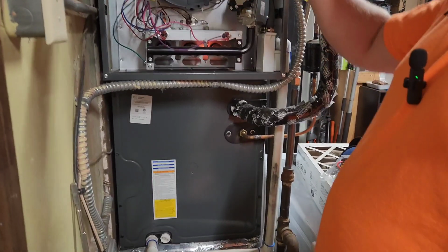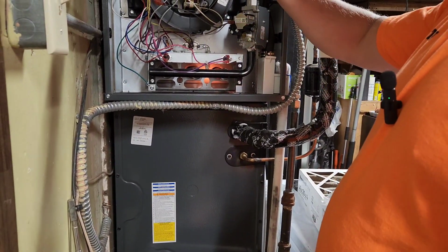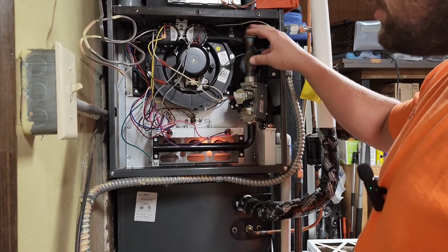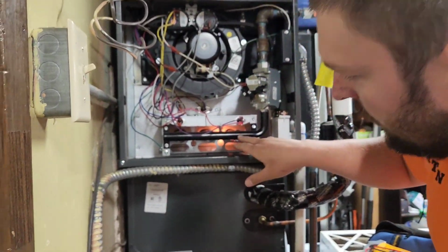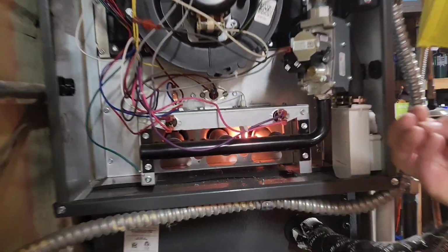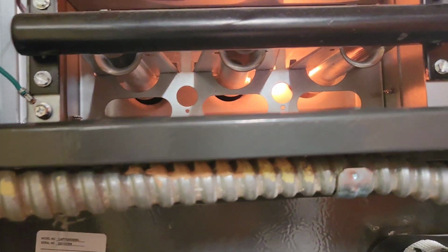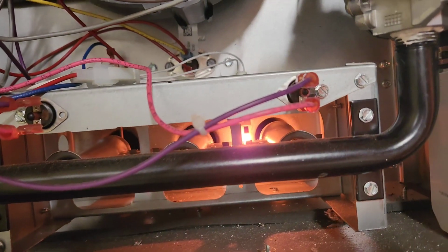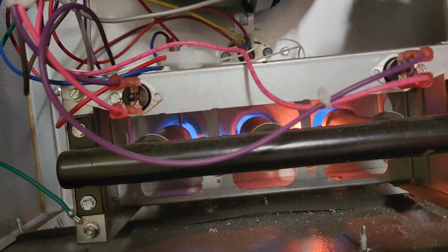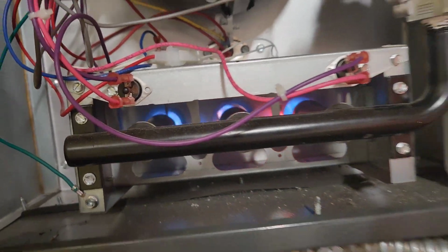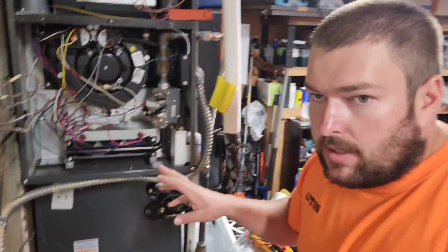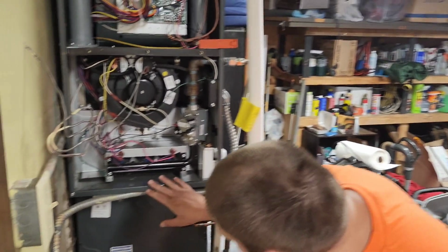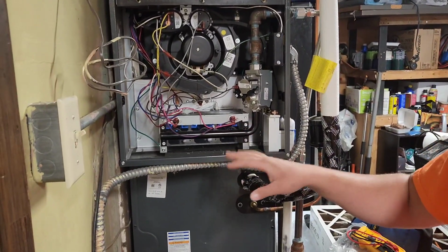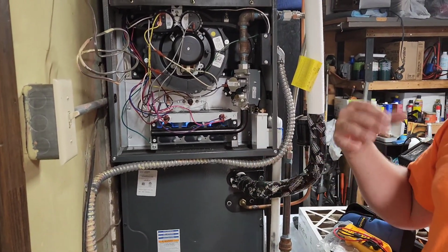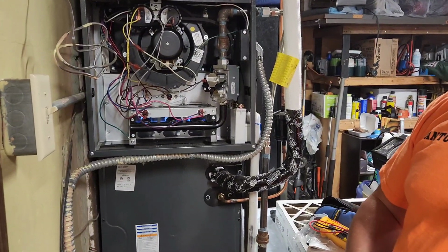Once the inducer motor and the vacuum switches prove that there is negative pressure here, you see the igniter's coming on, it's just heating up. The board will give it like 15 to 30 seconds before it actually kicks the flame on. Now you have your flame. During maintenance, what we will do is we'll check your flame color. We want to see that blue color. We don't want to see too much yellow because that's a sign of incomplete combustion.